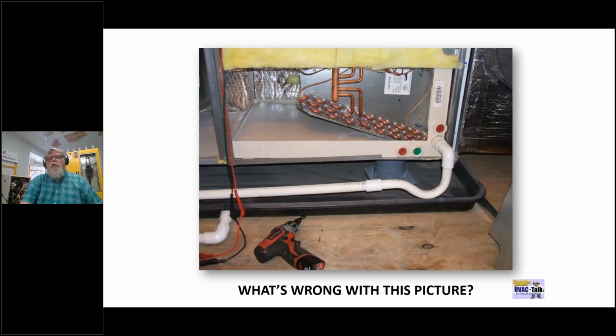On this piece of equipment here, if you pay attention to it, you'll notice that they actually connected the drain into the wrong openings. This unit could be used vertically or horizontally, and somebody got in there and put it into the wrong opening. So that's wrong. It's supposed to be in the green line at the bottom. If you look at it, you might think one doesn't look higher than the other, and it may not be, but there's actually a slope on that pan. On the inside, when you look in there, that one is a little bit higher. It's like part of the plug is blocked on the higher one.